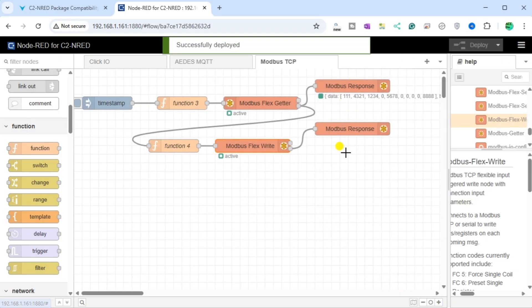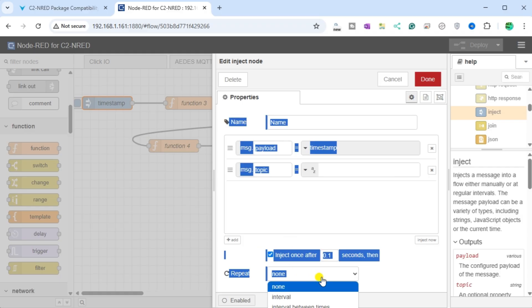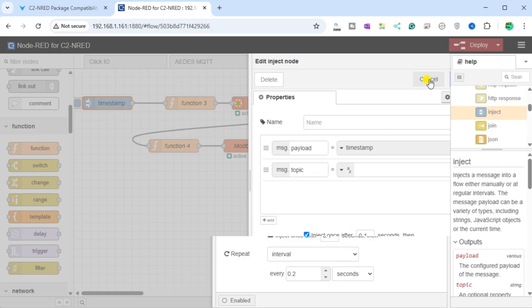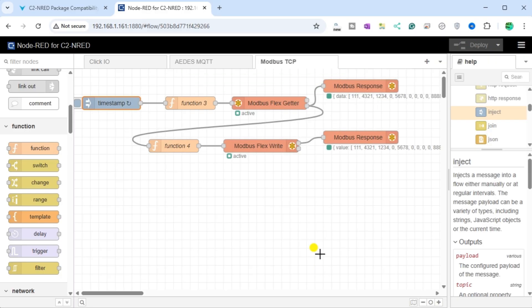Select Deploy to write the program into the C2NRED module and execute our flow. Verify using the Modbus Response nodes that everything is working as expected. We will change the Inject node to trigger communication for our flow automatically. Double-click on the Inject node and change the Repeat interval to 0.2 seconds — the communication will happen every 200 milliseconds, or 5 times a second. Select Done, then select Deploy to write this program into our C2NRED module. The Modbus Response node will show the information returned from our BRX Do-More PLC under the Data Array, and the Modbus Response node for the write will show this same data written.